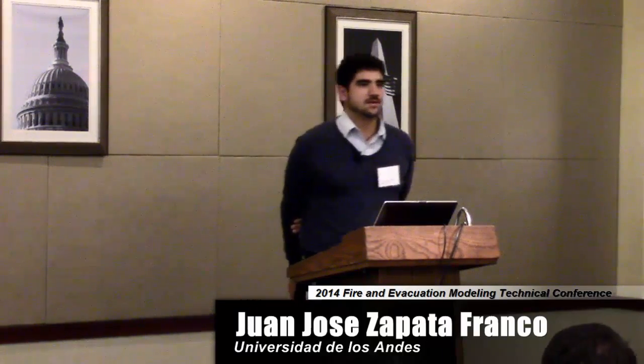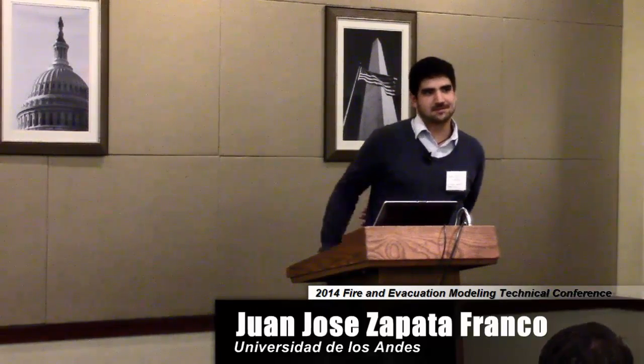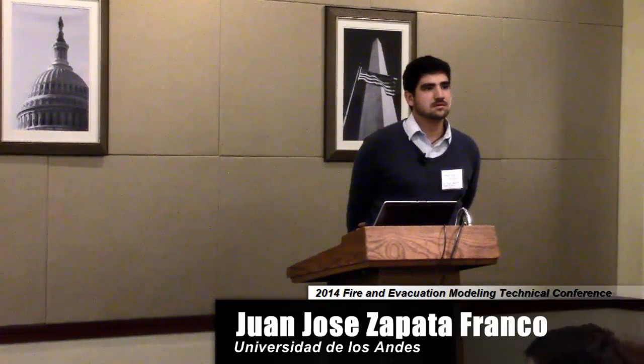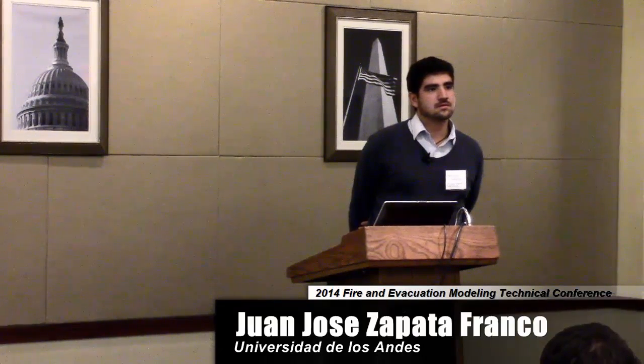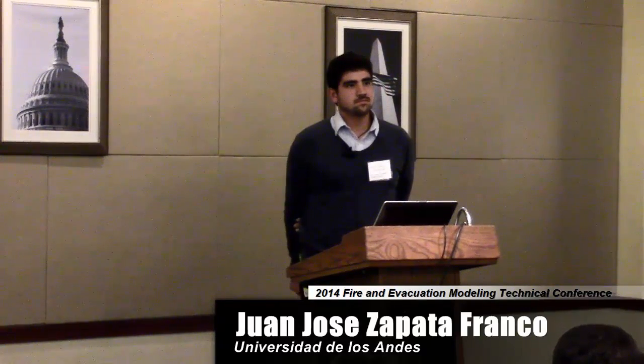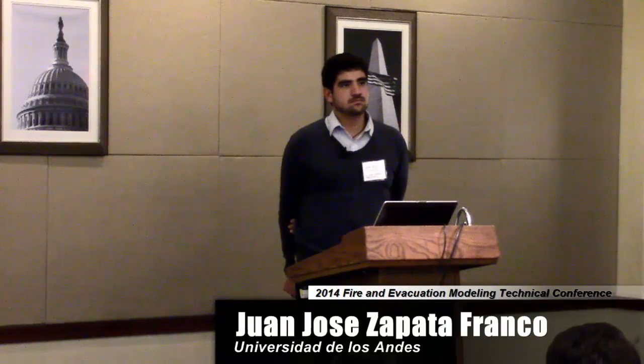Patrick Coirou from Belgium. I want to know why you chose the MQH correlation to predict hot gas layer temperature. I'm sorry, can you repeat that? Yes, I want to know why you chose the MQH correlation to predict hot gas temperature in your model. Because this applies only for natural ventilation conditions. And if we have forced ventilation or a closed door, is it possible to use your tool in this case?